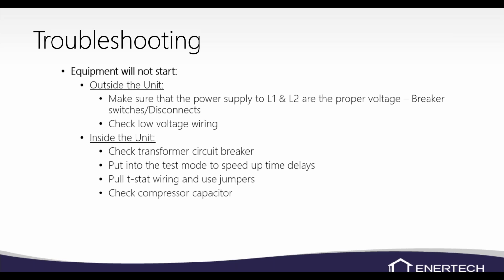Make sure we're checking the compressor capacitor. Look for any swollen or bulging capacitors, or if it's leaking any kind of fluid. Capacitors fail quite often, I should say, I shouldn't say quite often, but capacitors do fail. So make sure you're checking the capacitor.